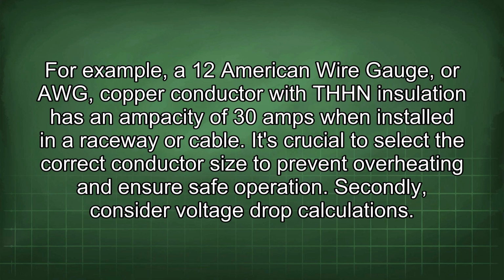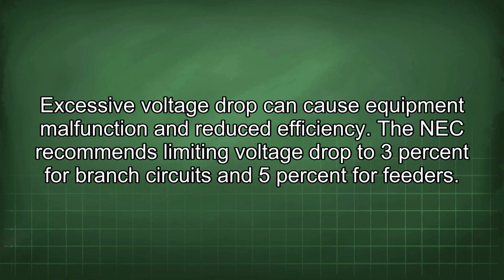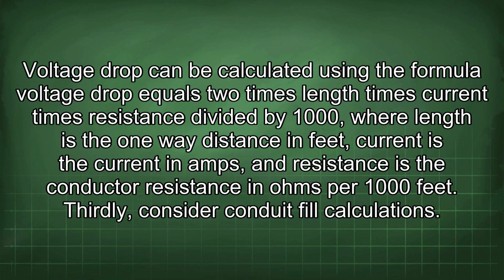Secondly, consider voltage drop calculations. Excessive voltage drop can cause equipment malfunction and reduced efficiency. The NEC recommends limiting voltage drop to 3% for branch circuits and 5% for feeders. Voltage drop can be calculated using the formula voltage drop equals 2 times length times current times resistance divided by 1000, where length is the one-way distance in feet, current is the current in amps, and resistance is the conductor resistance in ohms per 1000 feet.